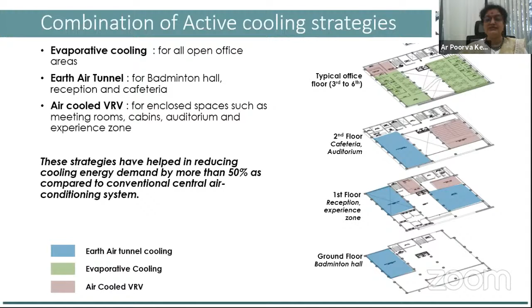Here, three different types of cooling systems have been used. For open offices, we felt evaporative cooling could work better. For the badminton hall, reception area and cafeteria, we did the earth air tunnel. And for cabins with closed spaces, we had an air-cooled VRV. These strategies have helped reduce almost 50% of the cooling energy demand compared to a conventional centralized air conditioning system.